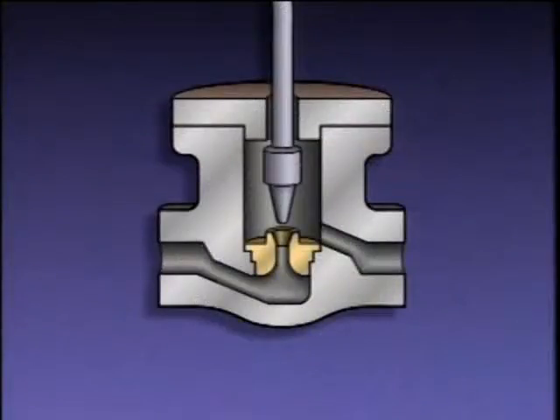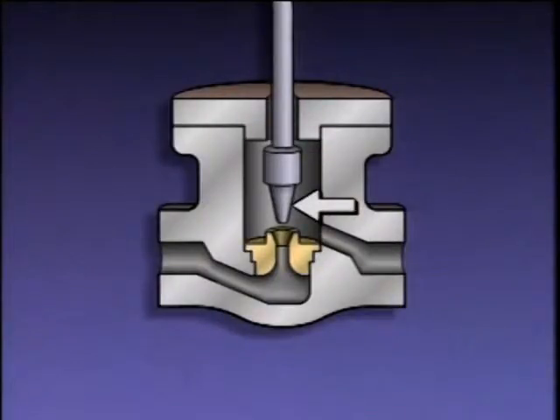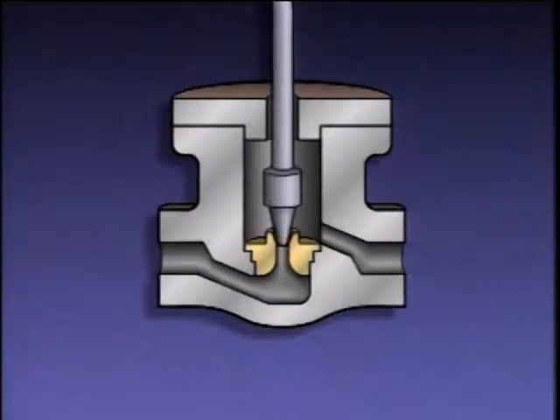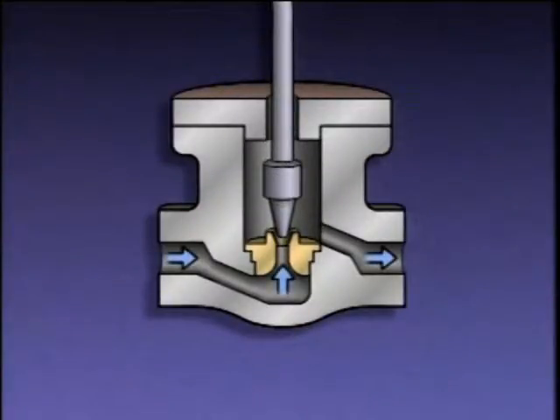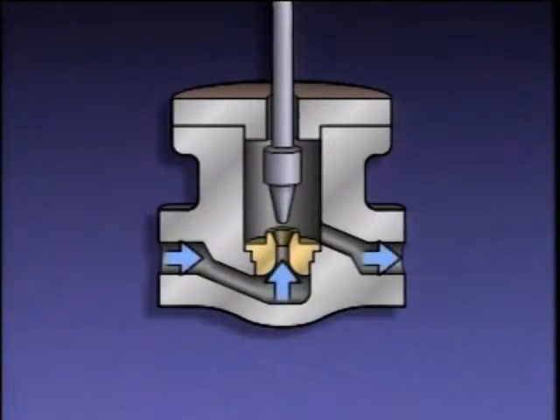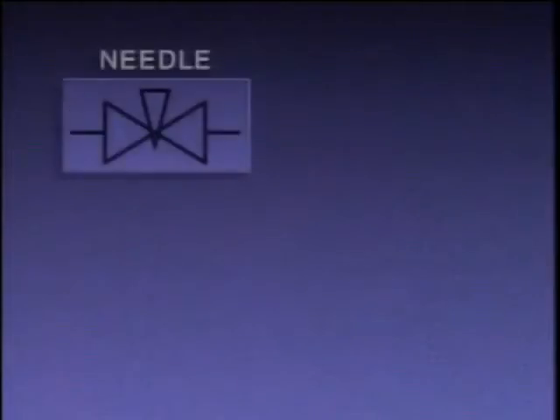A needle valve has basically the same parts as other globe valves, but its disc is shaped like a needle that extends deep into the seating area. A small movement of the stem causes a small, gradual change in the flow rate, giving the needle valve an extremely fine throttling ability. On a piping system diagram, a needle valve generally looks like a specific symbol.